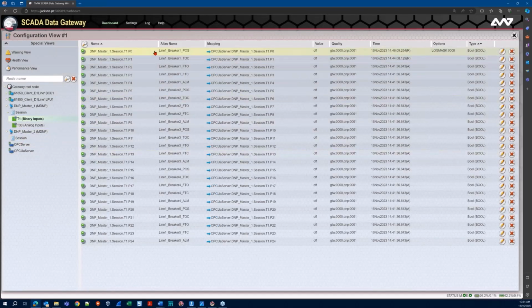And I don't know about you, but when I create points manually, I always like to give my points intelligent names. And that's what I've done up here ahead of time on DNP Master 1. So you can see that I've used alias names such as line 1 breaker 1 position, or FTO might indicate fail to open, fail to close, or just maybe more general alarm. And I have this for each breaker that I might have. Let's say I have 5 breakers in this particular bay or line.